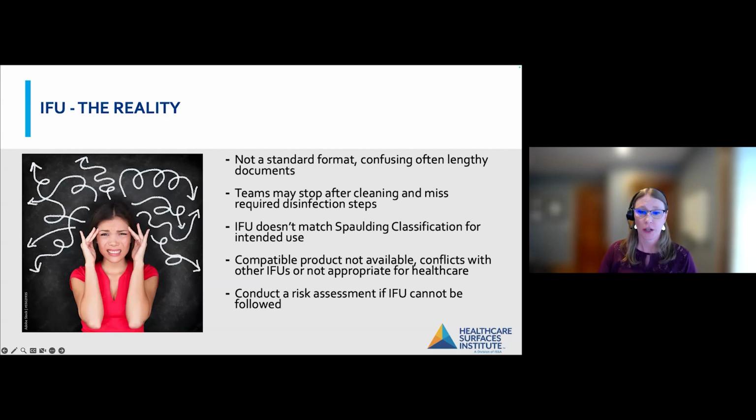Or you may have to reach out to the manufacturer of a disinfectant product that you're using to see if they have done testing for the instruments or equipment to see if it's compatible from that end. A lot of times the disinfectant companies have done studies to basically look at the type of material that's used on common products that they would be disinfecting. So then you can take that and say, okay, this piece of equipment was made with this type of plastic.